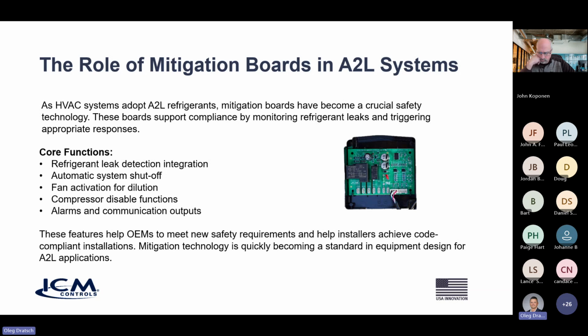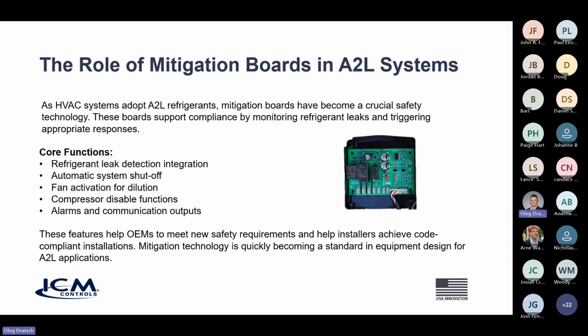So for years, ICM Controls has produced and really perfected an A2L mitigation board. Our board has been tested, and it's been deployed in tons and tons of units across the country. This board has been deployed for years. This board works. It has refrigerant leak detection capabilities. It's able to automatically shut off your system. When it senses a leak, it's able to turn on the fan and really expel any A2L refrigerant that has leaked in your system.